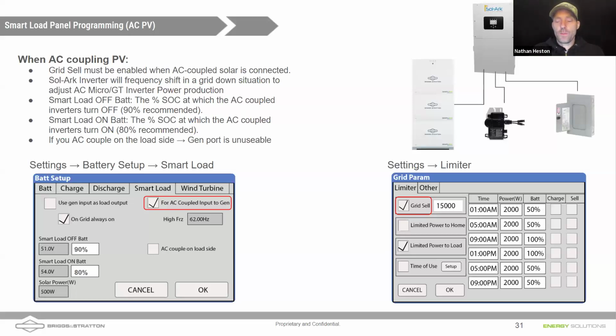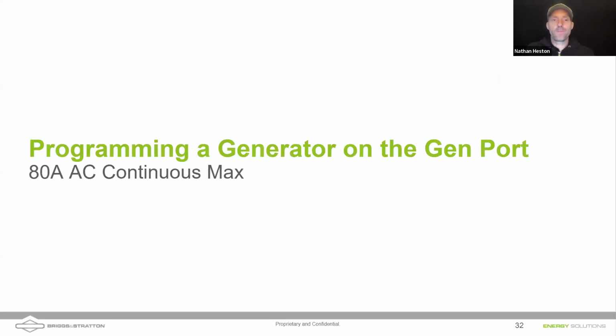But that's just a little bit of a buffer so we don't damage the batteries. Keep in mind, if you do have AC coupled solar coming in on the gen port, you do have to have grid sell enabled. So you'll need to make sure that you have that interconnection agreement. Generally, people that have AC coupled solar on their roofs typically already have that interconnection agreement in place.